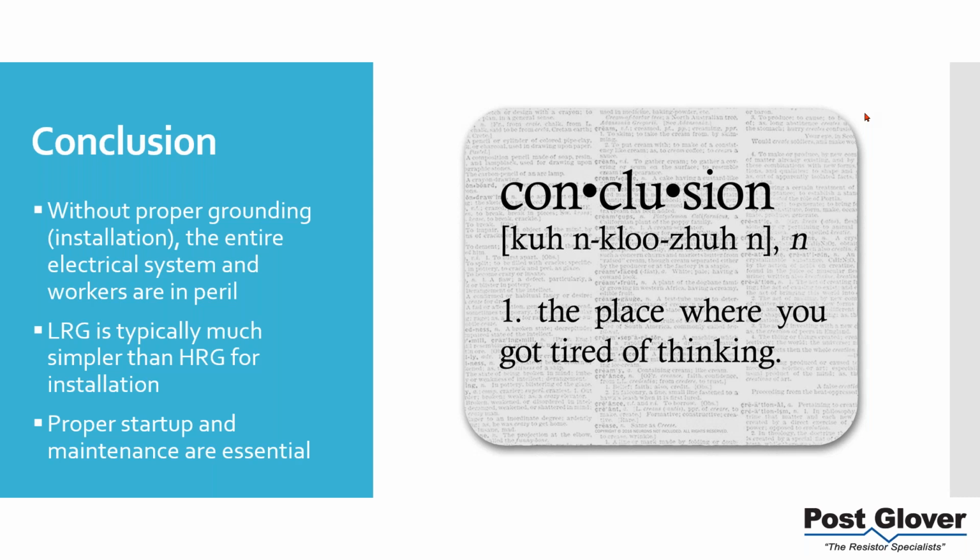You just need to know that temperature requirement and make sure that the delta T of that resistor plus ambient is going to be below that value. The standard temperature rise is 385 degrees C on a high resistance ground system. You're going to be doing much lower than that, usually half or less, so once again we're increasing the size of the resistor. As long as you understand that, we can definitely do one, but you're going to have a bigger resistor.